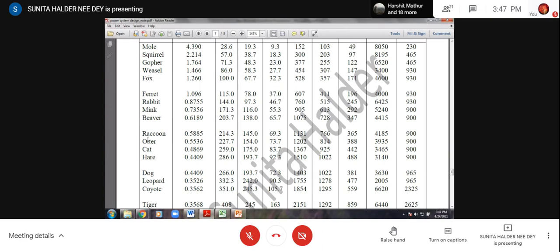You must remember when resistance is lesser, that is obviously good. But if R equal to point less than 0.5, you can take cat, hare, dog, leopard, anything of that. But we should choose cat, not hare. Why? Because when the resistance is lesser, that means cross sectional area is higher, so it is a solid conductor. So the conductor will be heavier, and along with that, the cost will be higher. So we shall take as much as possible near to 0.5.